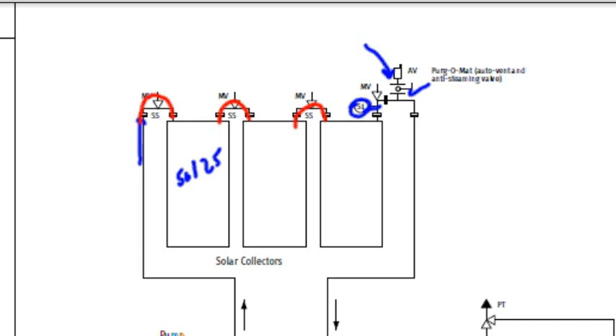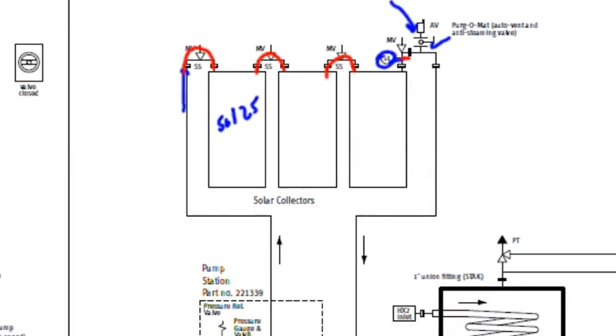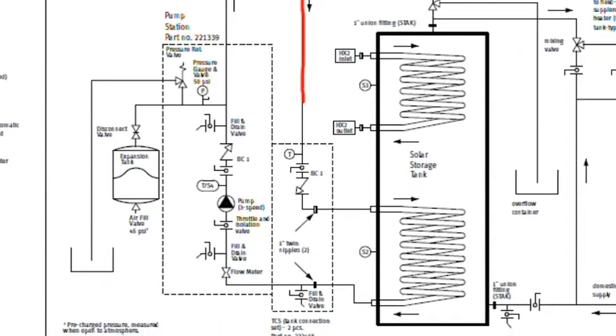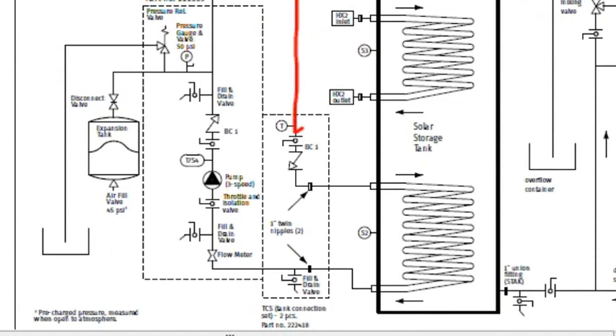The automatic vent leads that air out and then I have fluid that's going to leave, go through here, through another valve body that's going to turn on or off. I'm going to go through a check valve. This check valve right here will keep thermal fluids from flowing backwards at night. We don't want that. We want the solar thermal fluid to flow in one direction.